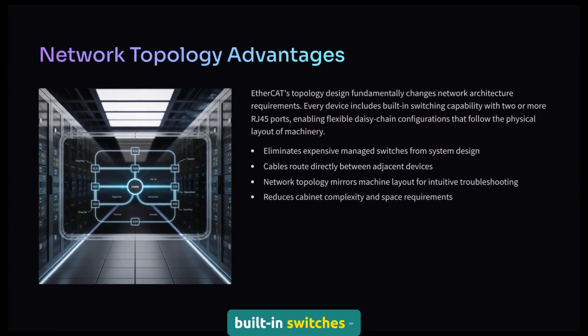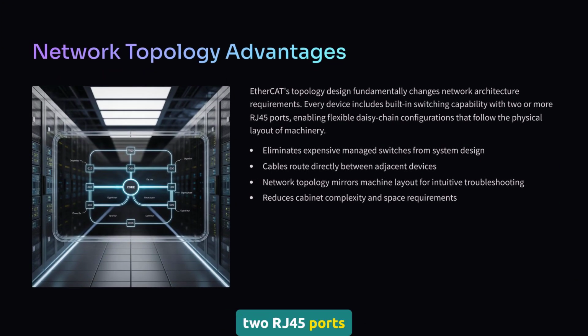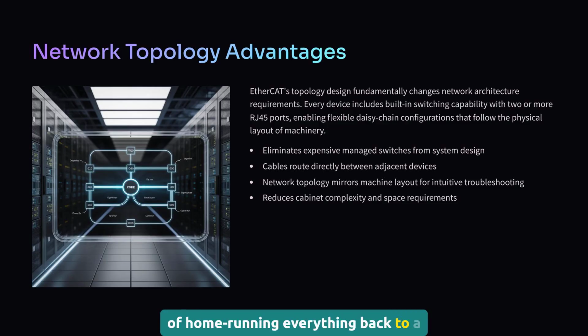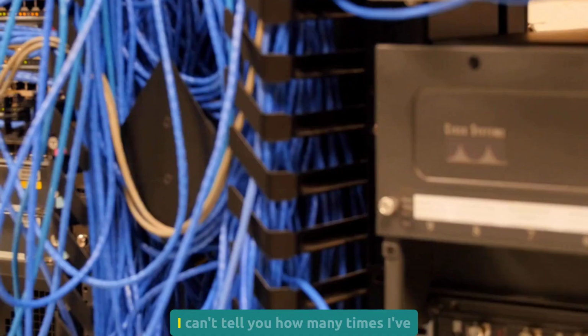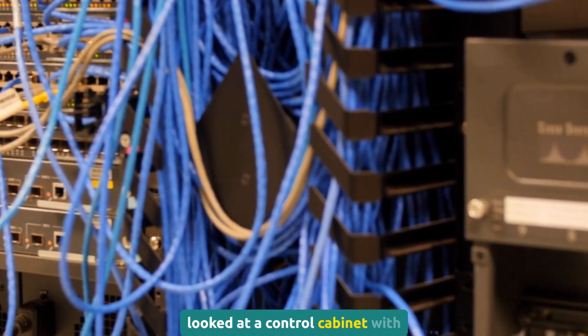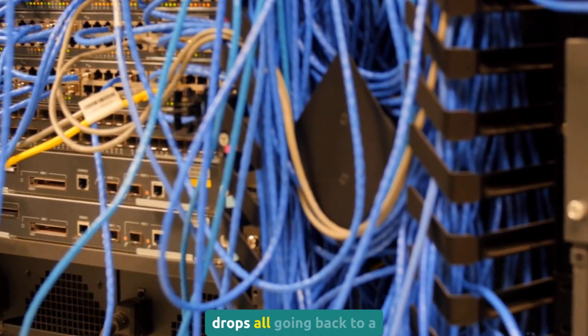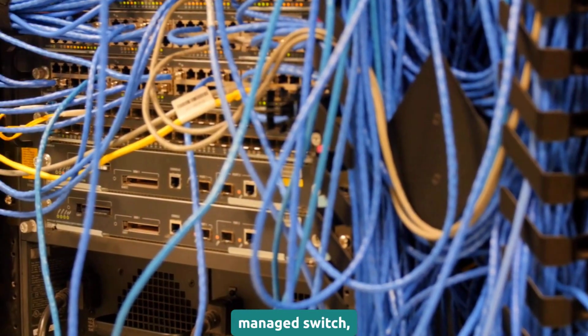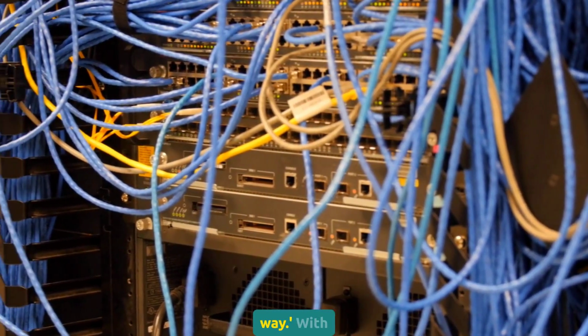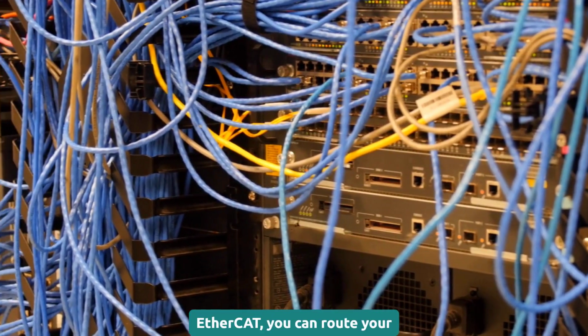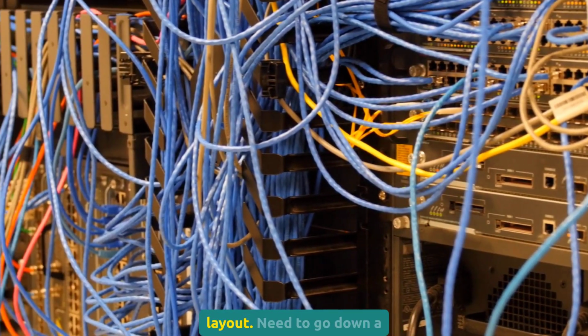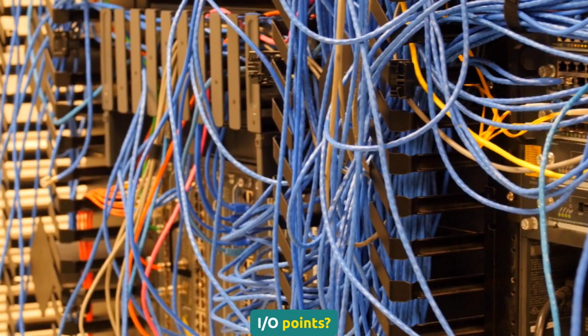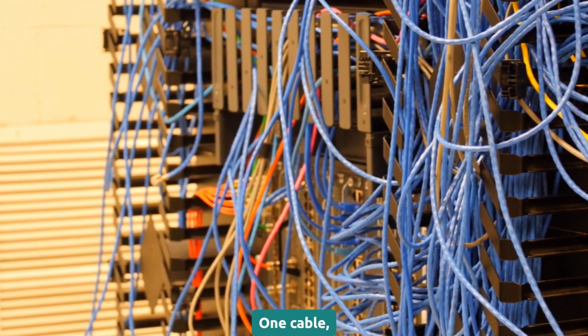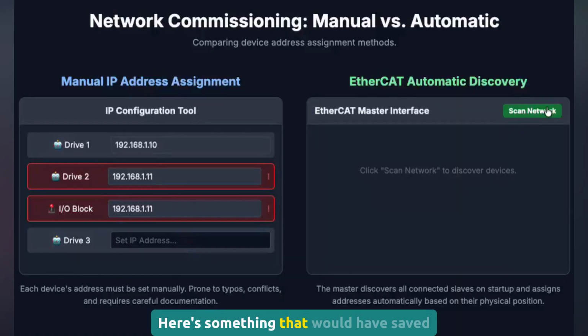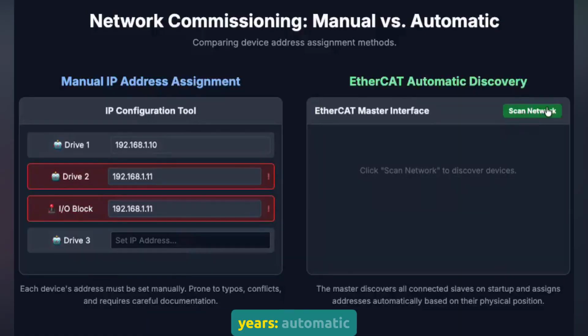EtherCAT devices have built-in switches. 2 RJ45 ports minimum. This means you can daisy-chain devices instead of home-running everything back to a central switch. I can't tell you how many times I've looked at a control cabinet with 48 Ethernet drops, all going back to a managed switch, thinking, there's got to be a better way. With EtherCAT, you can route your network to follow your machine layout. Need to go down a conveyor line hitting 20 I/O points? One cable, daisy-chained.